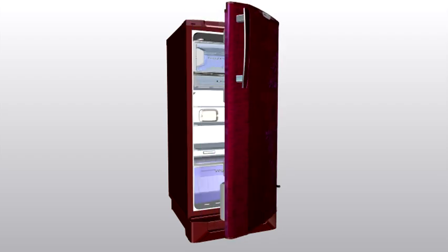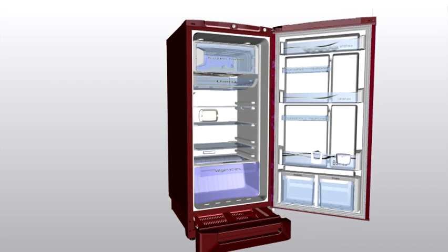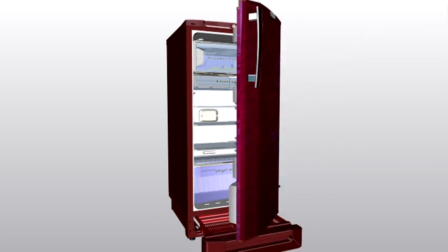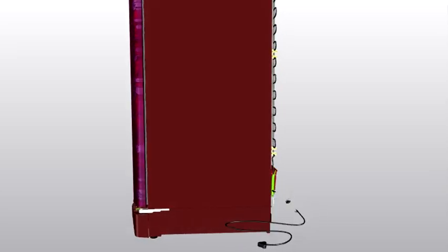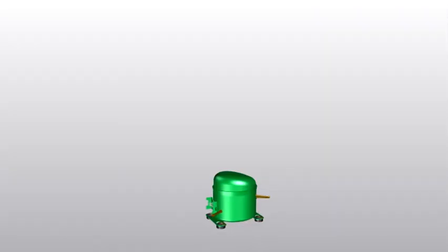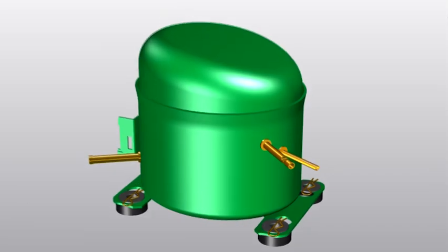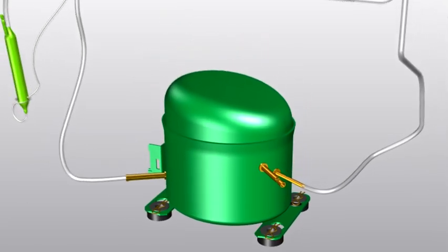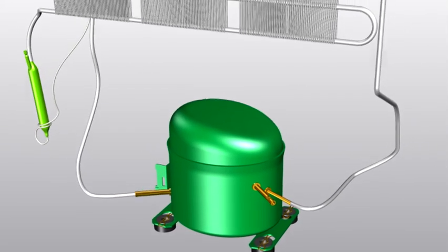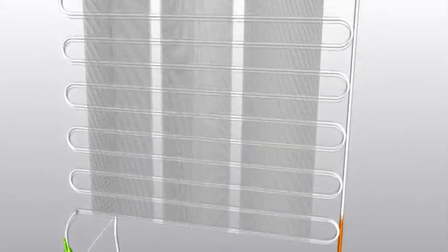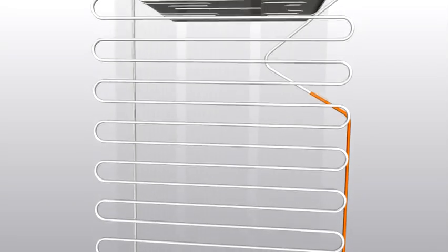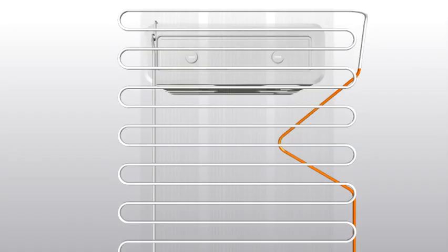Refrigeration cycle operations. When the compressor is initially switched on, it sucks refrigerant from the low side of the system, compresses and discharges it to the high side of the system. This creates a very high pressure difference, which is essential to create refrigerating effect. Low side pressure of 5 to 10 psig and high pressure of 120 to 140 psig.